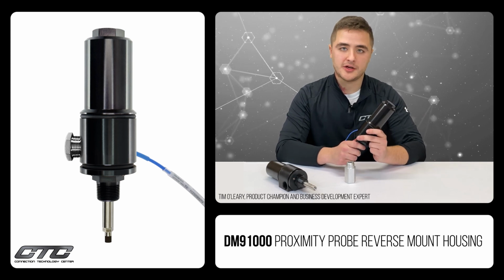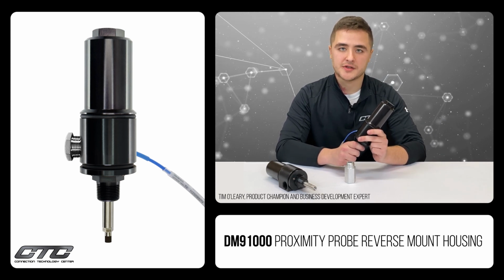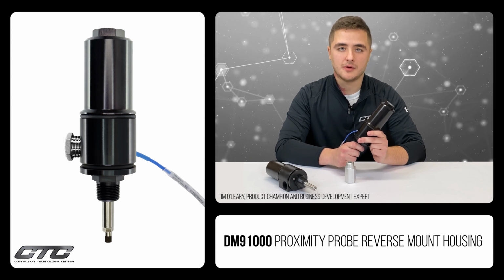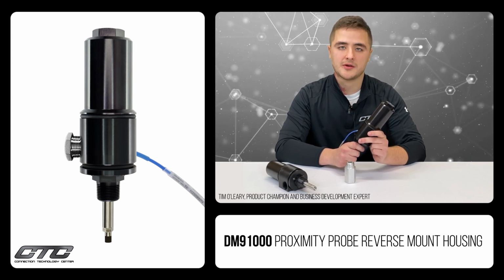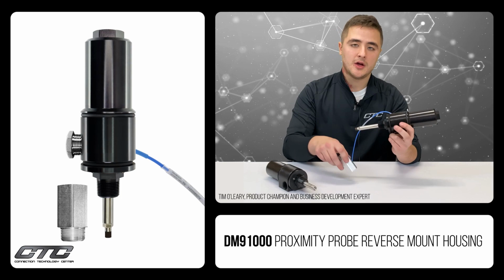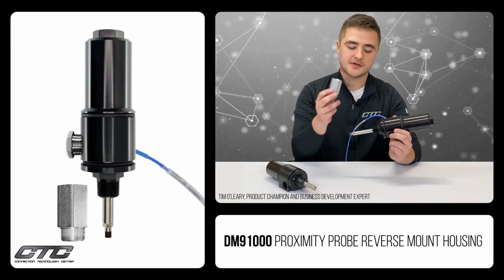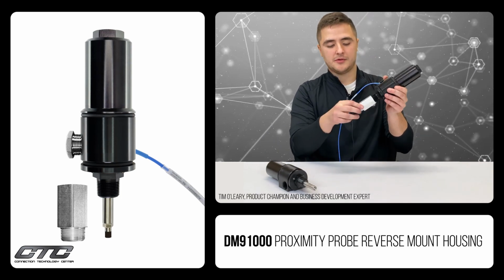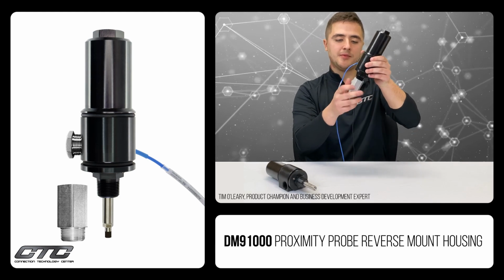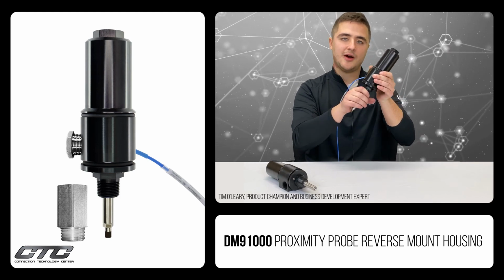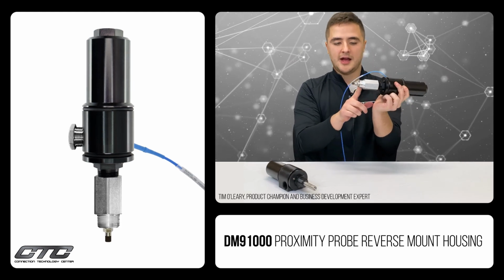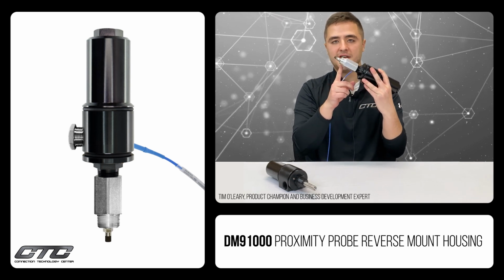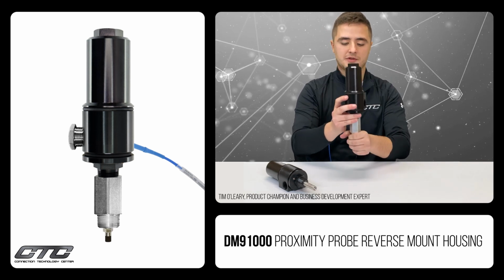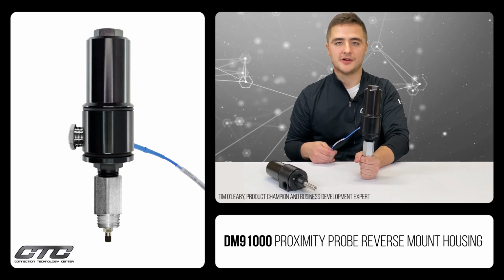If there are clearance issues on the surface of the machine housing the reverse mount proximity probe housing will be installed on, we do carry different sizes of standoff adapters that will screw in right over that NPT fitting on the bottom of the housing. It has an additional male NPT fitting right at the end that can be screwed down to give you additional clearance when needed.